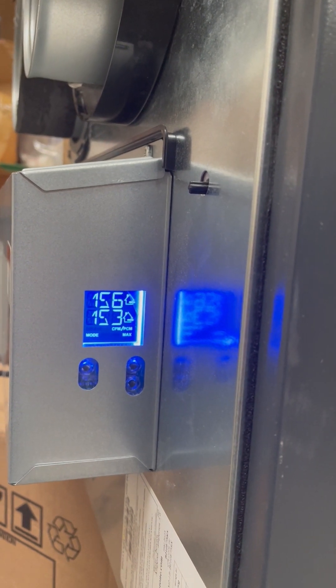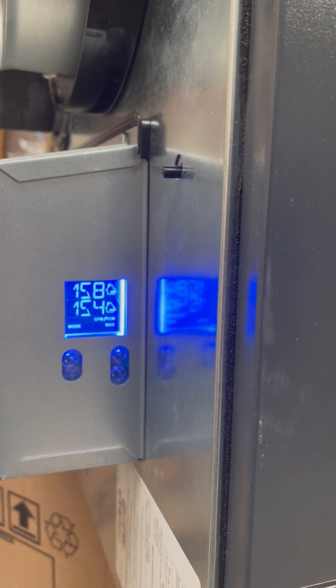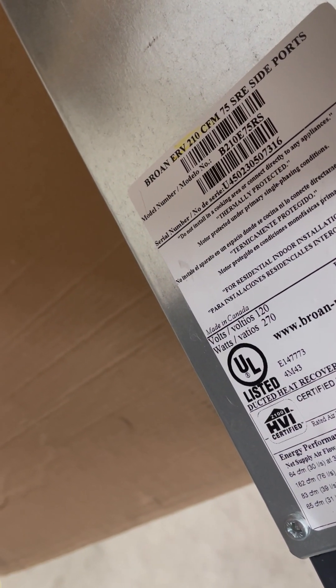It's interesting that after commissioning this unit — and I've got another one in a box right below here — it did the same thing. It had 163 CFM available out of the 200.